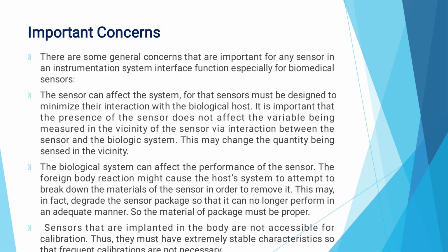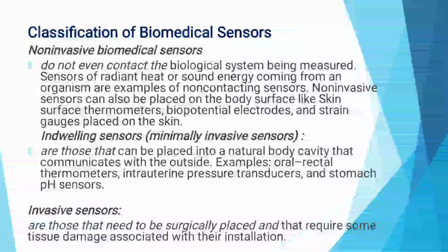Another important concern is calibration. Sensors placed inside the body cannot be frequently recalibrated. So the major thing to keep in mind is that biomedical sensors should have stable characteristics and long-term accuracy.